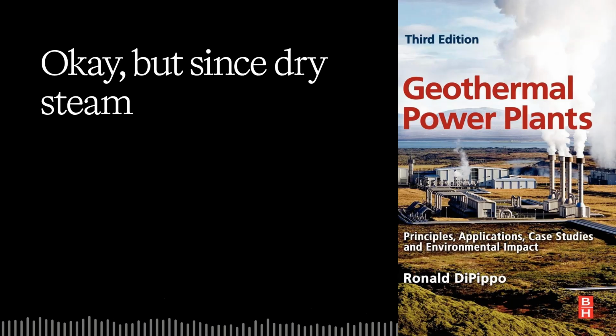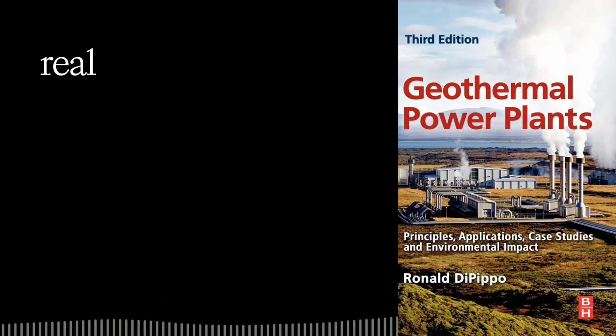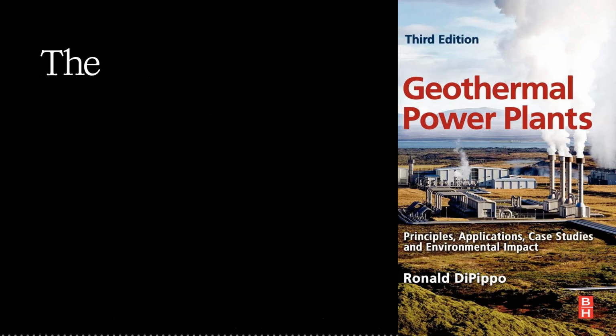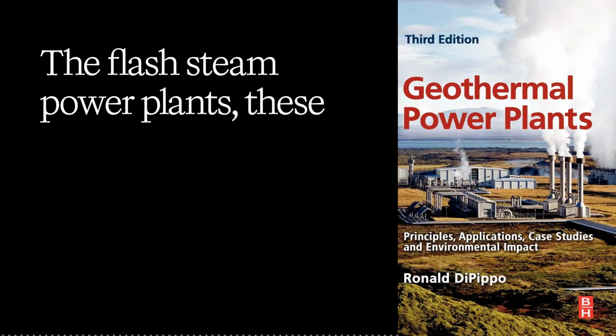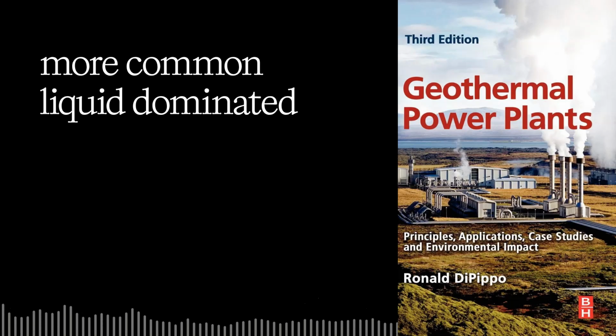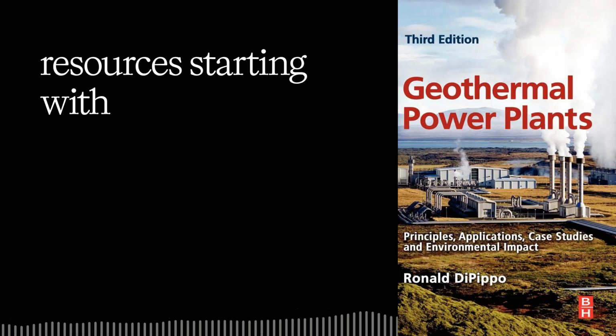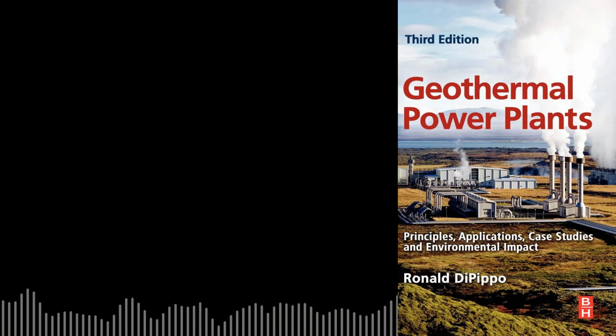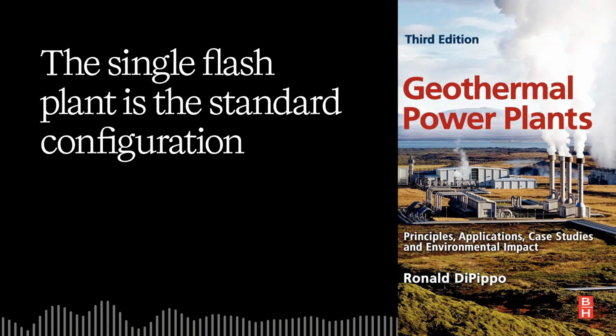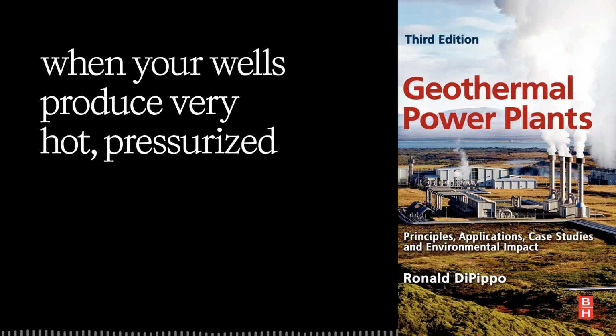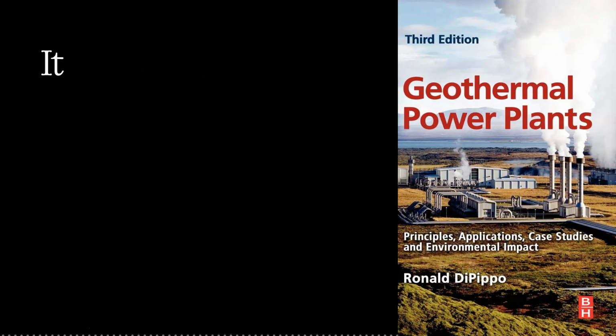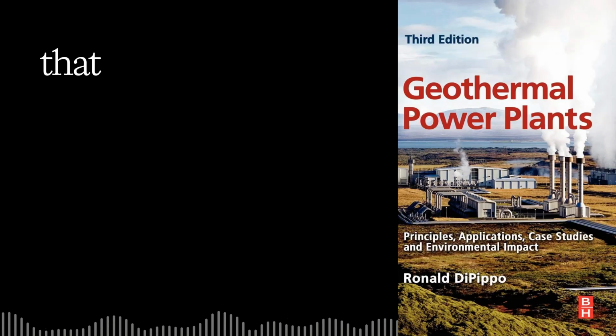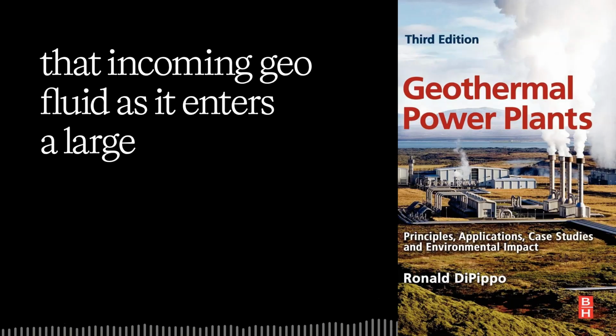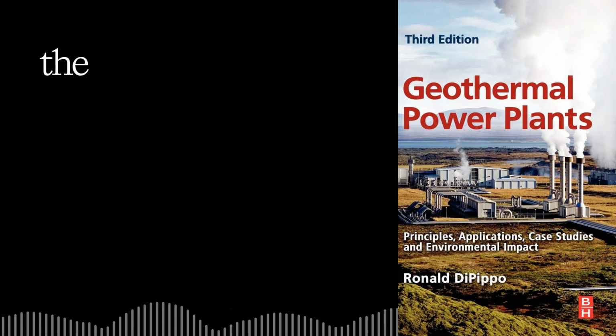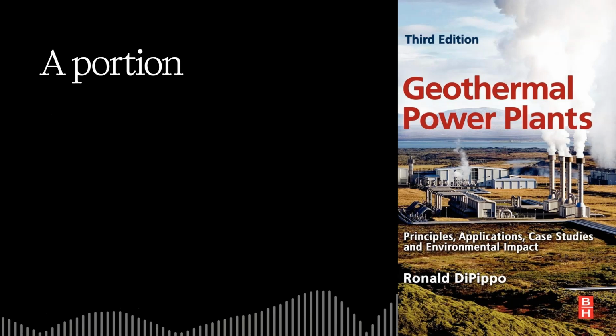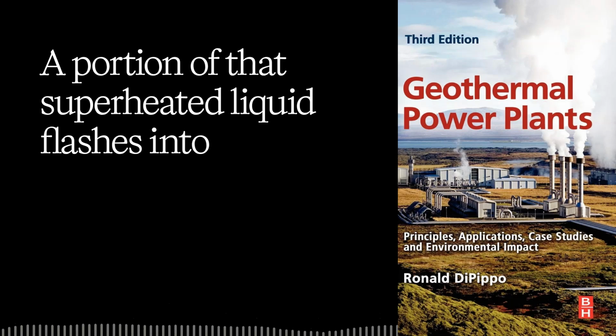Okay, but since dry steam is so rare, let's move to the real workhorses of the industry, the flash steam power plants. These use the much more common liquid-dominated geothermal resources, starting with the basic single flash design. Right. The single flash plant is kind of the standard configuration when your wells produce very hot pressurized liquid water, often called brine. It works by drastically reducing the pressure of that incoming geofluid as it enters a large vessel on the surface. And reducing the pressure makes the hot water boil. Instantly. A portion of that superheated liquid flashes into steam.